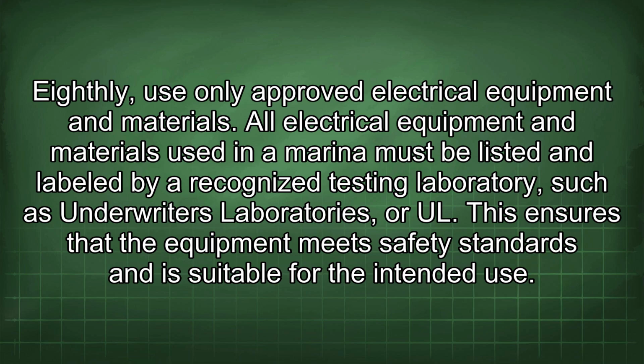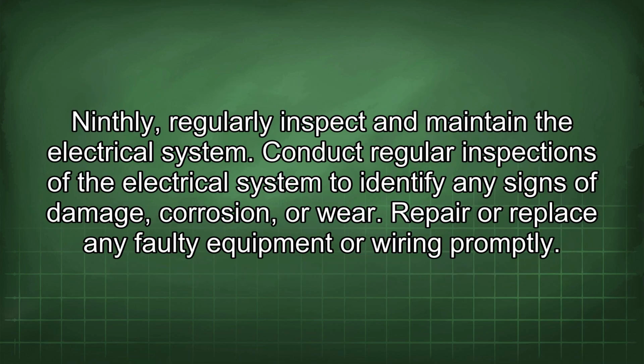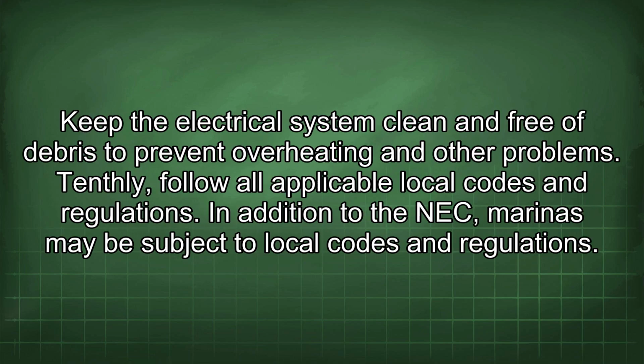Eighthly, use only approved electrical equipment and materials. All electrical equipment and materials used in a marina must be listed and labeled by a recognized testing laboratory, such as Underwriters Laboratories or UL. This ensures that the equipment meets safety standards and is suitable for the intended use. Ninthly, regularly inspect and maintain the electrical system. Conduct regular inspections of the electrical system to identify any signs of damage, corrosion, or wear. Repair or replace any faulty equipment or wiring promptly. Keep the electrical system clean and free of debris to prevent overheating and other problems.